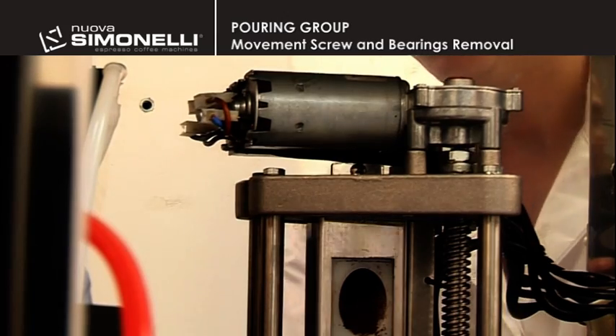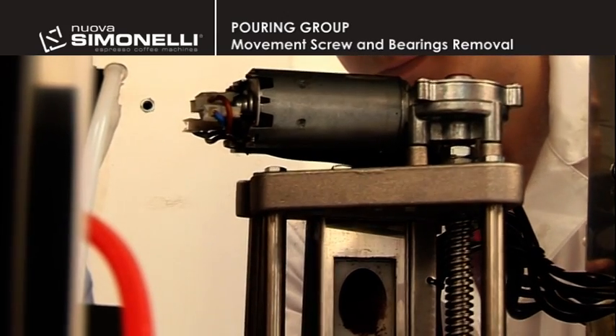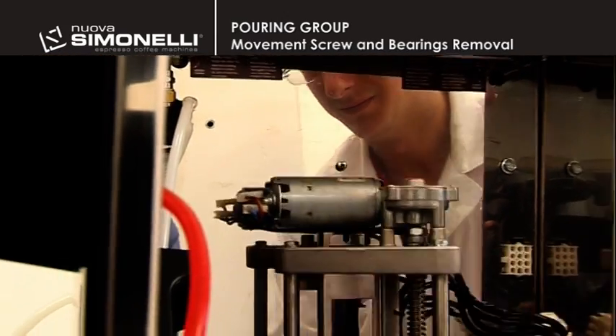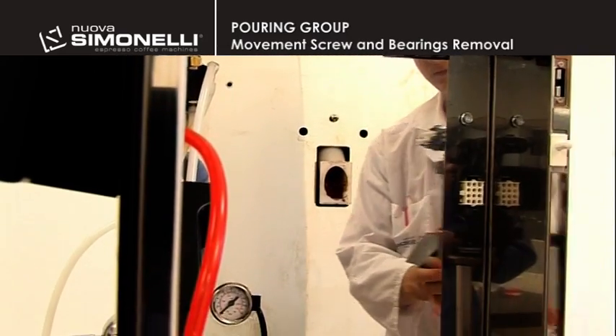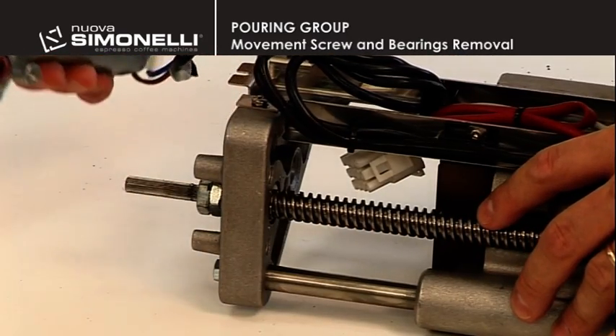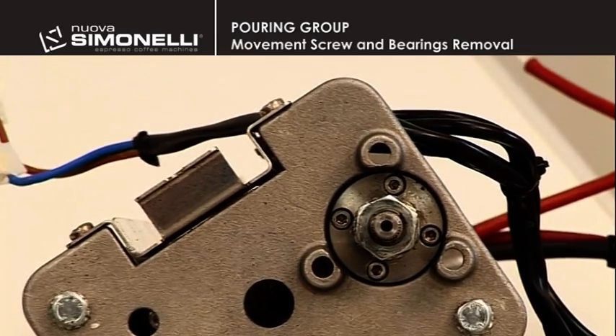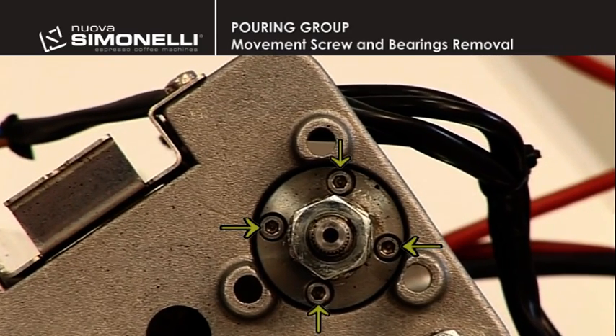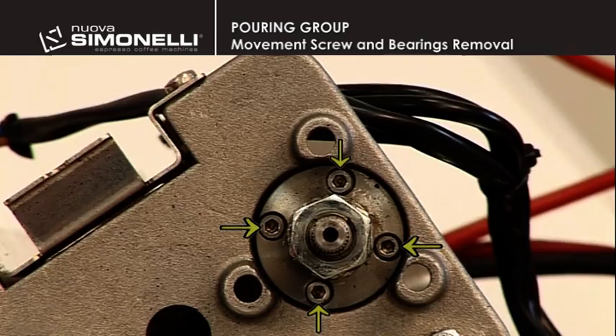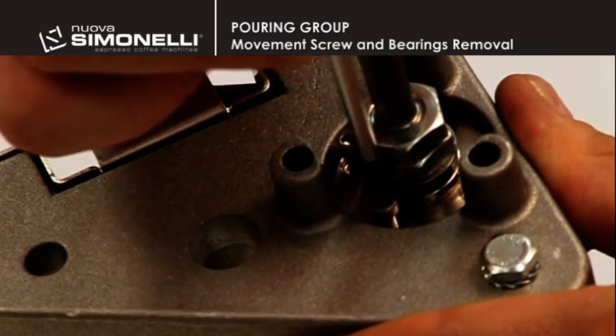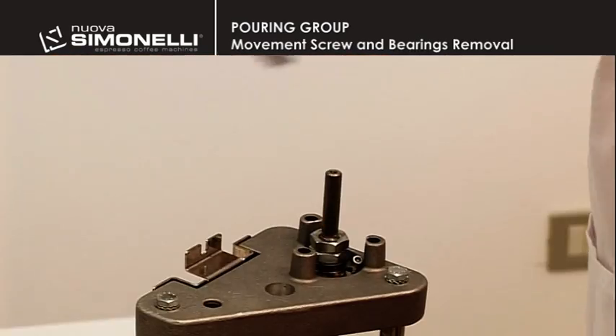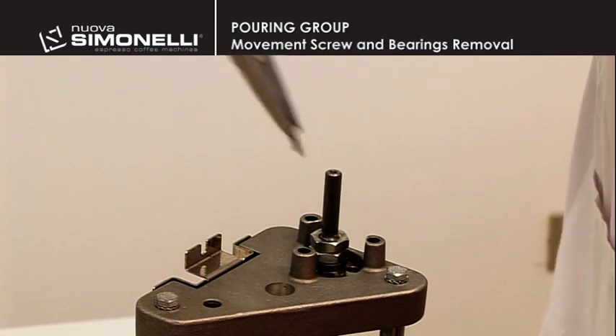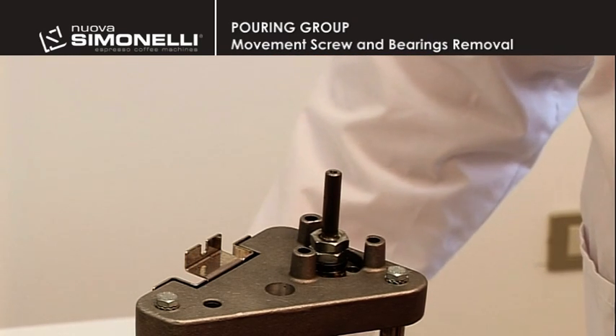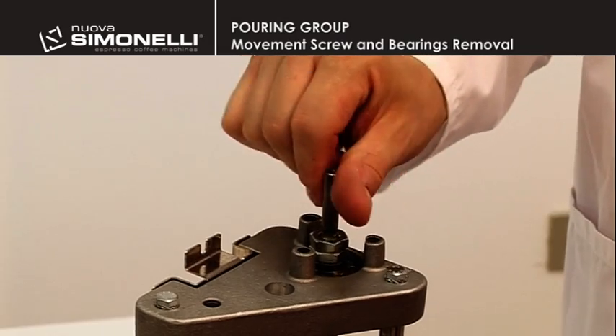Movement screw and bearings removal. To remove the movement screw, it's necessary to remove the group from the machine. Take out the motor and then remove the four 2.5mm Allen screws from the top support of the group. This way, it's possible to remove the worm screw by loosening it.